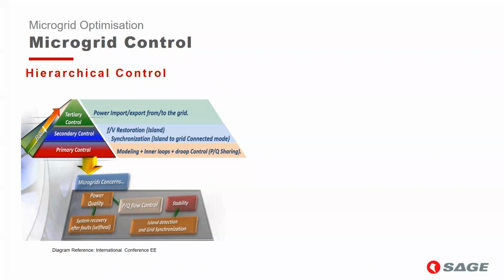Secondary control is responsible for voltage and frequency deviations caused by variations in load, as well as can be designed to satisfy power quality requirements. The third level is tertiary control, which is responsible for power import and export to the grid and provides energy management.